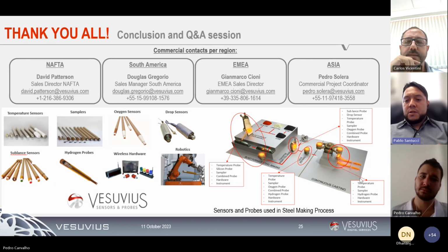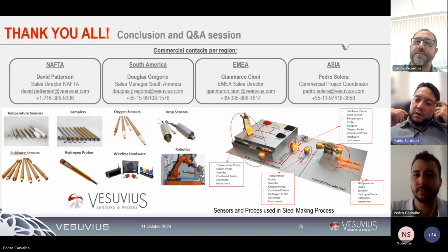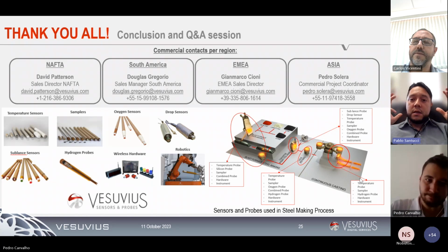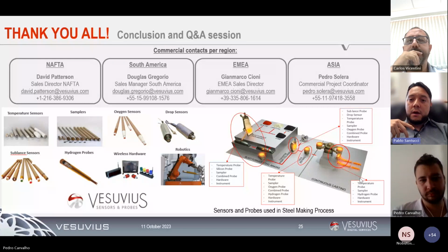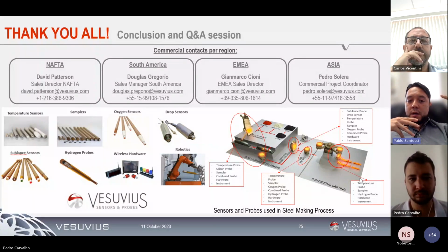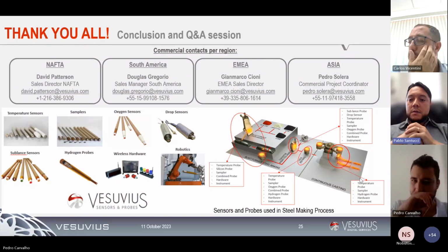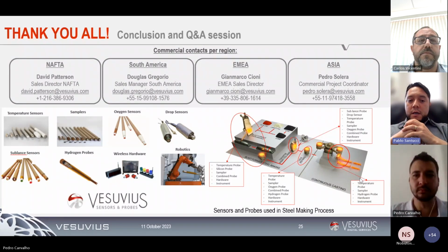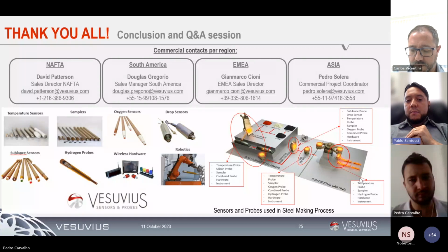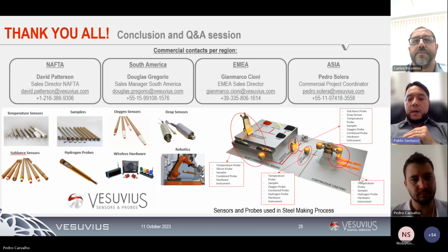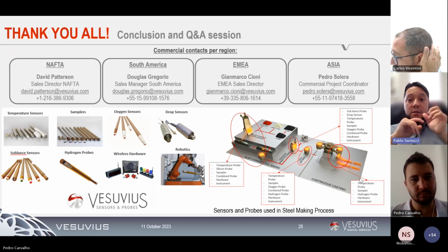Vanderlei Marcos is asking whether the inert gas could be argon. The answer is yes, it's possible, because the thermal conductivity of argon is very similar, though not the same, in comparison to nitrogen. So argon can be used. However, our system has been calibrated at our manufacturing site using nitrogen. So every time a new request like that is made, we need to recalibrate our system based on argon and use argon as the carrier gas for that specific unit.